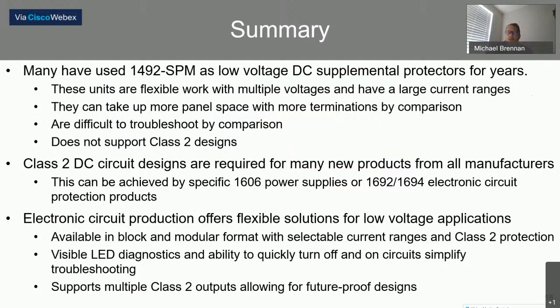So in summary, what we've seen is a lot of folks have used the SPM for low voltage supplemental protection for years. And the SPM is really flexible. You can use it with AC/DC. You can use it between 1 and 63 amps, so it has a really wide current range. They can take up more panel space because by comparison, they do have many more terminations. They're a little bit more difficult to troubleshoot, and they do not support Class 2 designs.